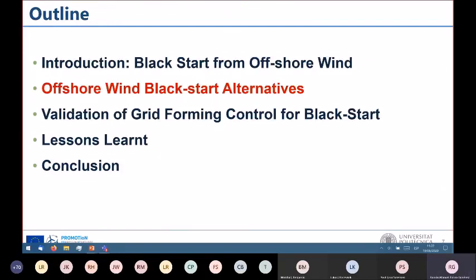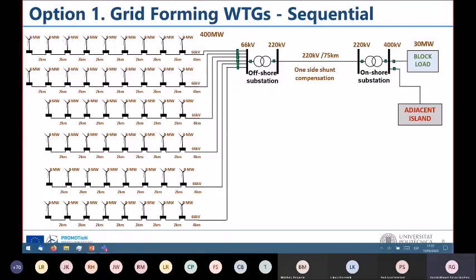Which alternatives have we been studying for black start? The first one is AC connected offshore wind with a cable of about 75 kilometers, 220 kV. We studied the sequential black start, which basically consists of a wind turbine with local energy storage powering up by itself when there's enough wind, then powering up the first string cable, then little by little all the rest of the wind turbines in the same string.